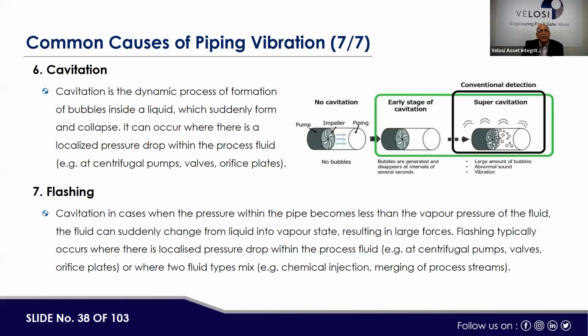Cavitation is another part. Cavitation is a process which we normally refer to in pumps. For example, if pump NPSH is not being provided by the upstream, like a vessel or the incoming upstream flow, and a gas is mixed in the fluid, there are bubbles and they burst all of a sudden. This bubble bursting causes cavitation and noise, and also causes high erosion on the impeller or the piping system. So cavitation is normally managed by proper controls, and mixing of gas in the liquid when it is being pumped should be avoided. Secondly, NPSH as per the applicable practices is required to be maintained.